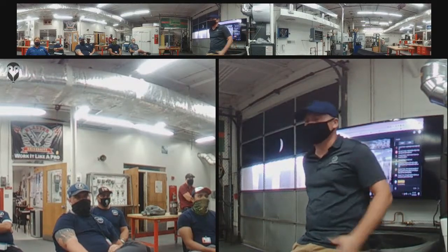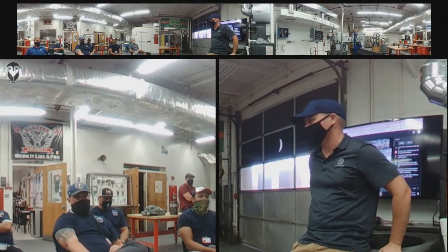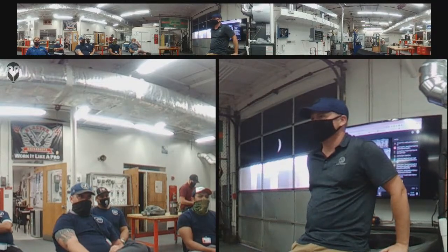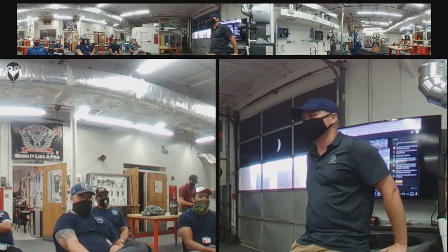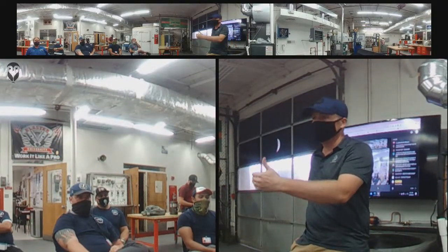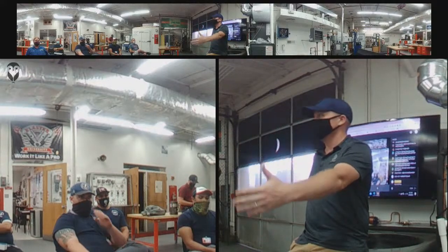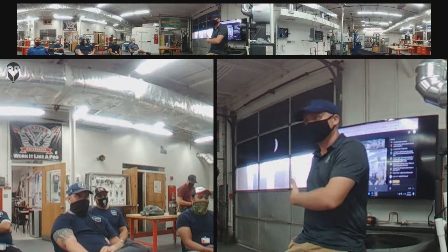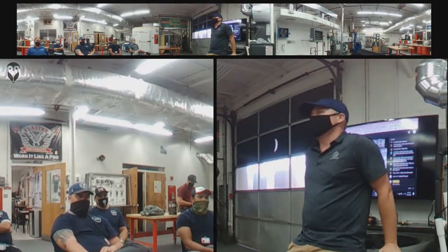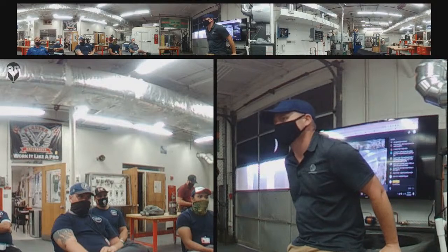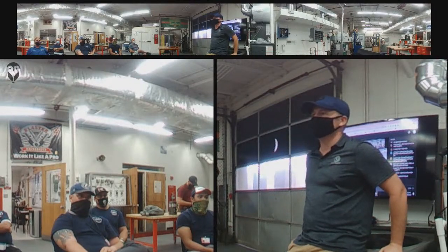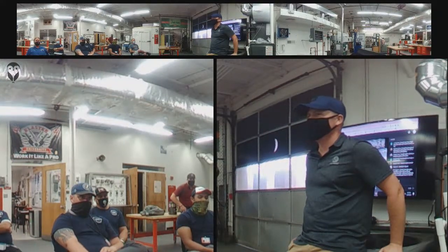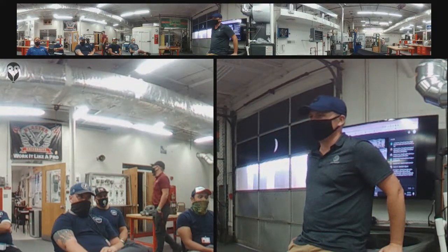Now, gas has been used safely throughout the country for a really long time. But of course, the challenge in Florida is that you don't have a lot of people who know how to work on gas properly, and that's why whenever we do a new gas furnace installation, we send Max out with the combustion analyzer to do a full commissioning, because it just terrifies me. Frankly, the way I did it for the first 15 years of my career now terrifies me to the extent that I am a little wary of gas, because we've just seen so many issues.